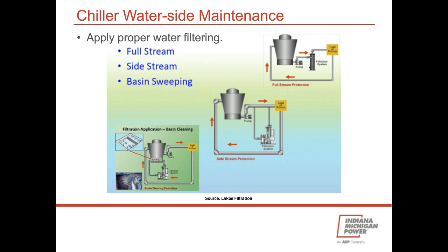That's usually done one of three ways, either full stream, side stream, or basin sweeping. And there's pros and cons of that. If you look here up in the top right, this is full stream. In other words, all the water going through the tower goes through the filter. It's going to create additional pressure drop, and increase system head, but it's going to be most effective in terms of cleaning all the water. You could just do a side stream where you take 10 or 20% of the flow at a time and filter that. That's pretty good for existing buildings. It's a lot cheaper than going to a full stream. Or you could even go and just do basin cleaning, which requires jets in the sump and removes dirt at the source. So that's pretty good for new or existing buildings.